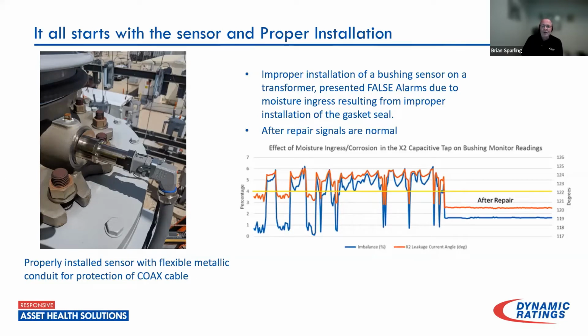We did have one case here where improper installation of the bushing sensor began to generate false alarms. It was due to moisture ingress resulting from the improper installation of the gasket between the bushing sensor and the flange of the bushing tap. What you see here, in blue, is the total imbalance current going up and down as the thing was breathing moisture. The leakage current, or the phase angle in this case, because we're measuring two things, leakage current and phase angle, gave a whole bunch of false alarms.